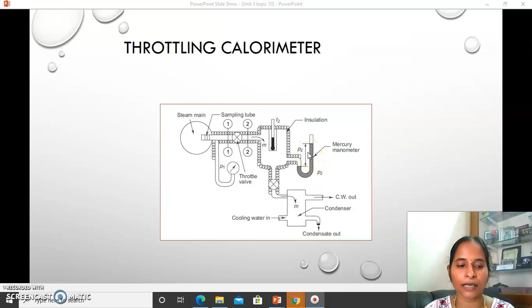Now it is measured, and finally you can exactly measure the quality. Again, here you can get the final pressure of the steam by using the mercury manometer. And for cooling the steam coming out of this calorimeter, a condenser is used. These are all the ancillary equipment used for measuring the pressure and to reuse the same steam again and again. You can leave this. The important part is where the steam is converted from wet steam to dry saturated or superheated steam. The quality of the throttling device purely depends upon how it improves the steam's quality, and it is also used for measuring the temperature as well as pressure of the outcoming steam.